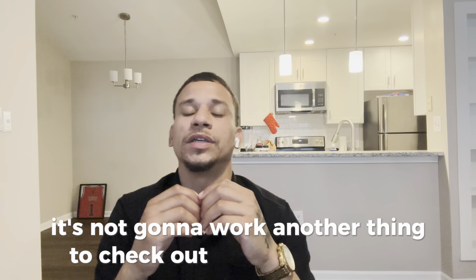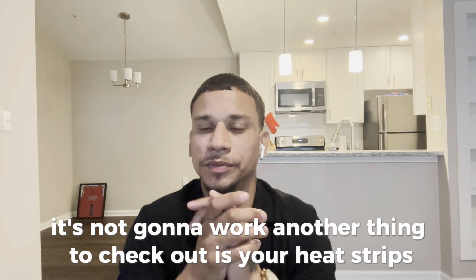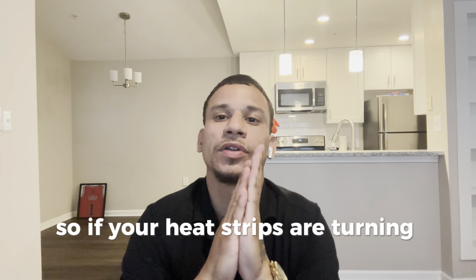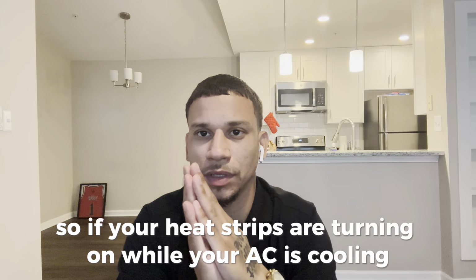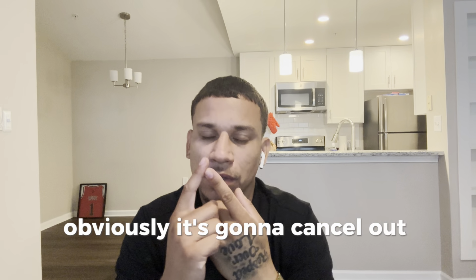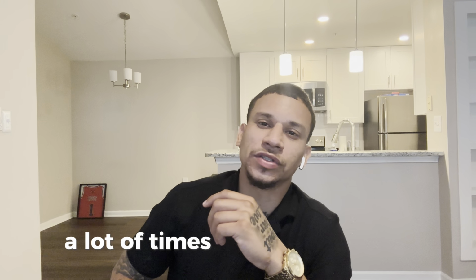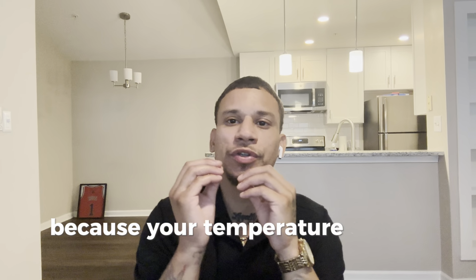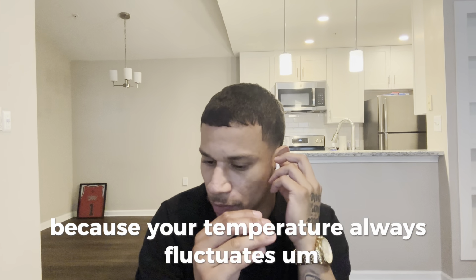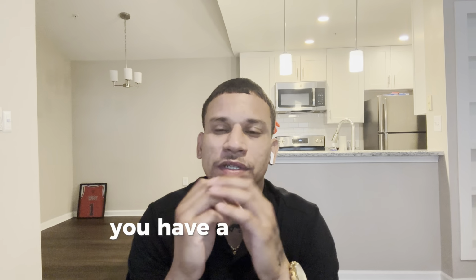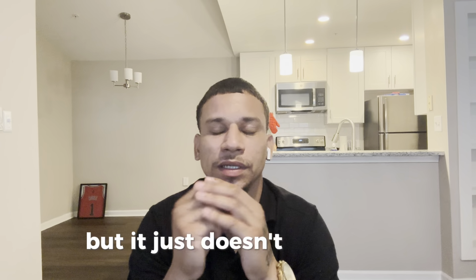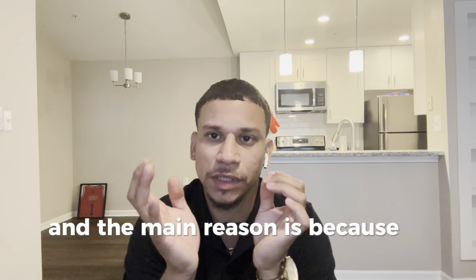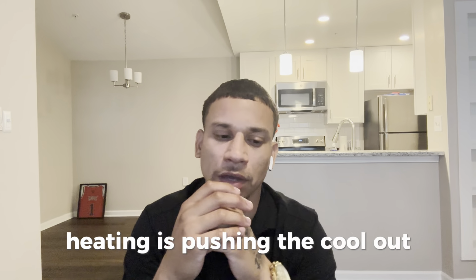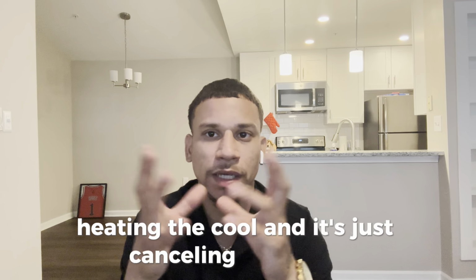Another thing to check is your heat strips. If your heat strips are turning on while your AC is cooling, obviously it's going to cancel out. A lot of times it's hard to tell because your temperature always fluctuates - it gets real close to the temperature set on your thermostat but just doesn't get there. The main reason is the heat strips pushing out heat while it's cooling, and it just cancels out.